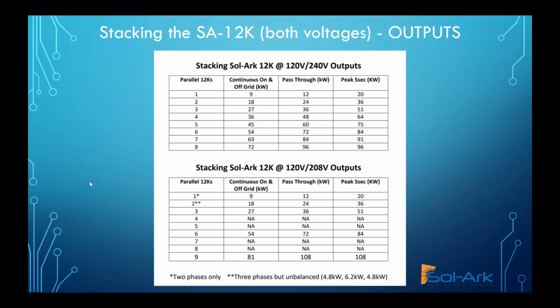I'm on mute, so I'll let Dustin talk about this briefly for just a quick second. This is the table, and it has to do with stacking. The top part is 120/240 volt. The bottom part is 120/208 volt, and it increases the capacity. As you stack these units, everything increases in terms of its continuous power, the pass-through power, the peak power, et cetera. Mm-hmm. So yeah, it just breaks down. If you're ever curious what your pass-through or peak power would be for a project and what you're needing, this is a good table to put in perspective how many systems would be required to meet the demand.